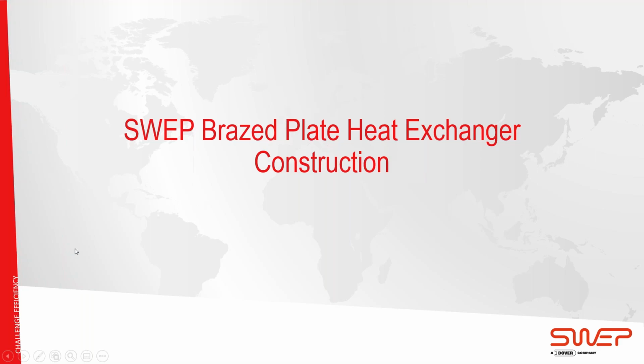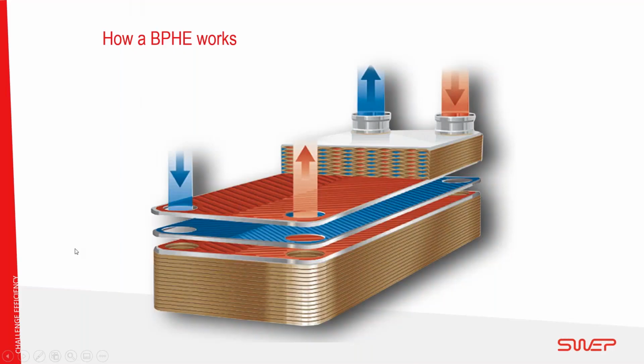Sorry, I skipped a slide there. Here we are. So this is the basic principle of a brazed plate heat exchanger. Essentially, you've got a hot and a cold media channel, and it's a simple heat transfer of energy. An example could be cold water cooling hot engine oil, or district heating from an energy center, the primary network, some of you may know it as, being used to generate domestic hot water in a residential apartment or any other commercial setting.